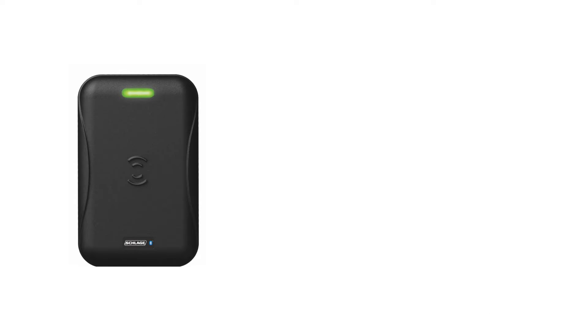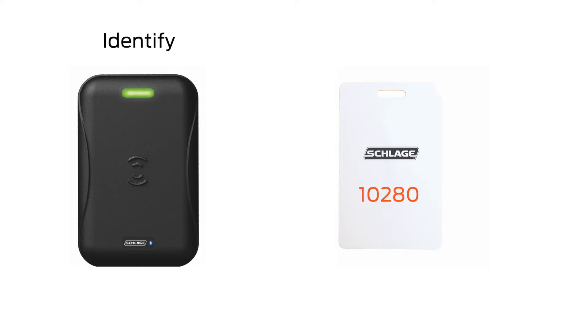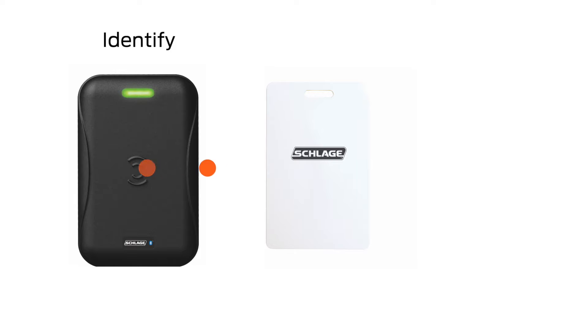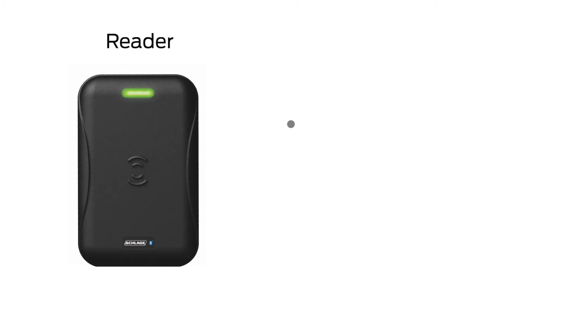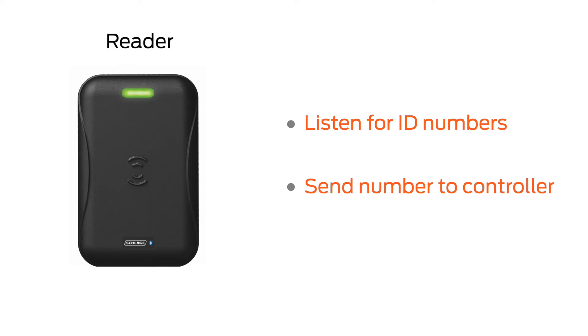Readers are usually a small plastic box mounted to the wall near the door. Systems will commonly use a card reader to gather information about the person. When a person approaches the door, they'll hold their card up to a reader. The card has an ID number electronically stored on it, and when the person holds it up to the reader, the reader provides the card with a little bit of power to transmit the number and receives it. Then the reader sends the ID number to the controller. The reader's jobs are simple: listen for ID numbers when people approach, and send the ID number to the controller.